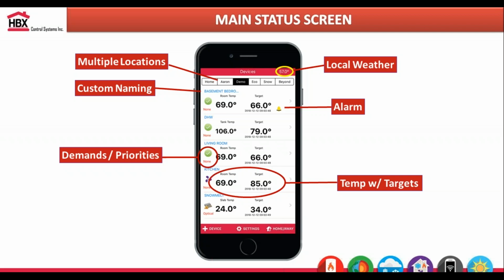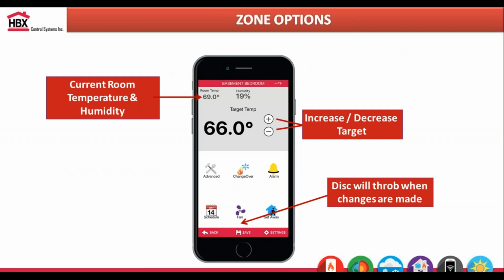You can implement your local weather on there, so you know how cold it is outside. On there you can put different priorities for heating to cooling. Typically you maybe want to use a zone for your domestic hot water, and you may want to put priority for that, or you may want to have priority for your kitchen or bedroom first thing in the morning. So make sure that those always get heated first before other zones that are typically not used through that residential or commercial application.